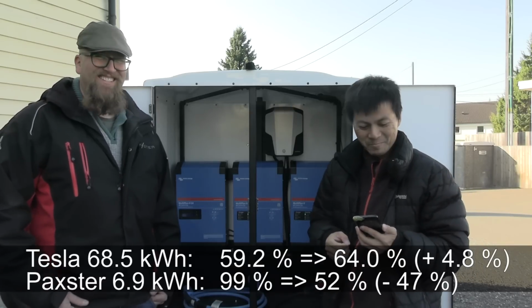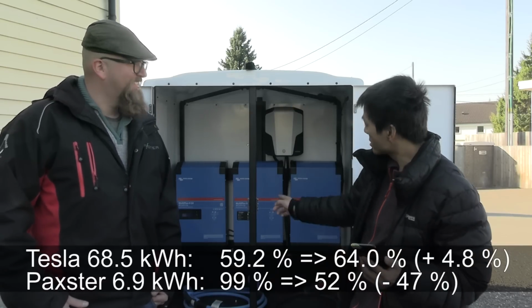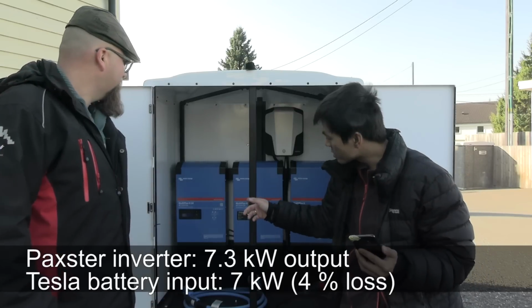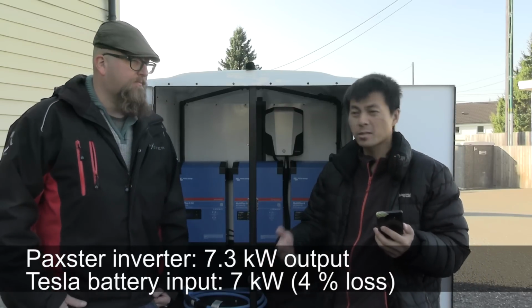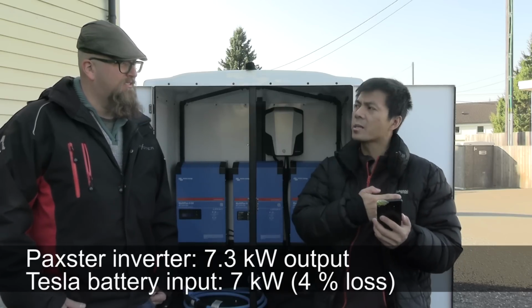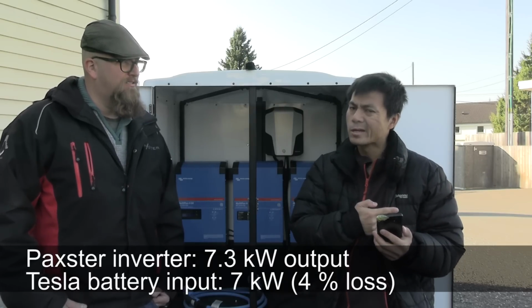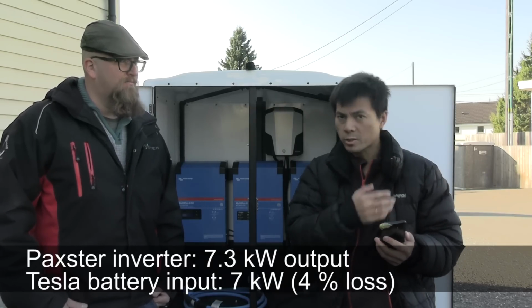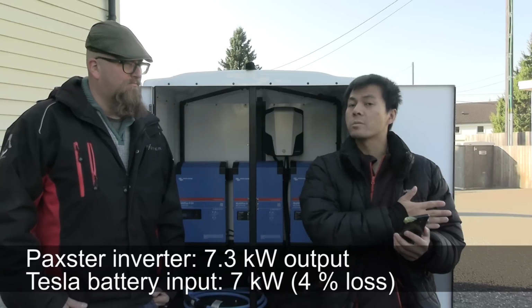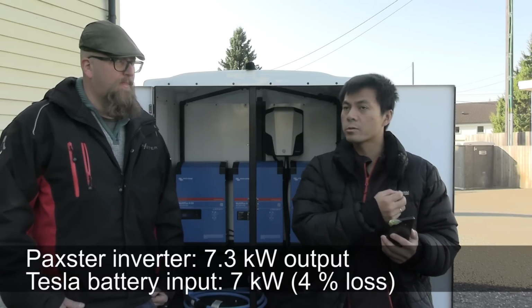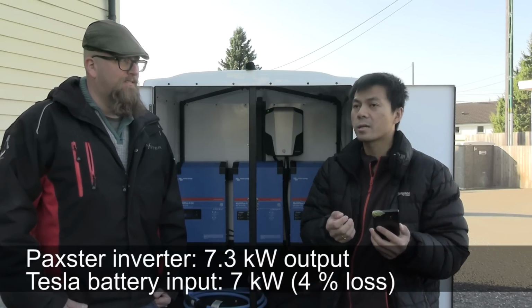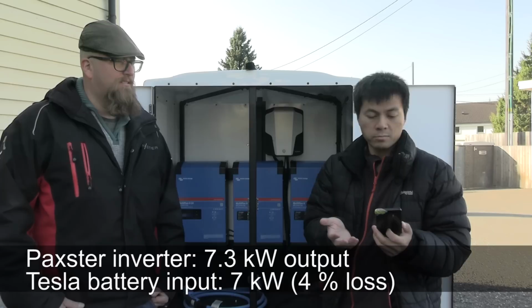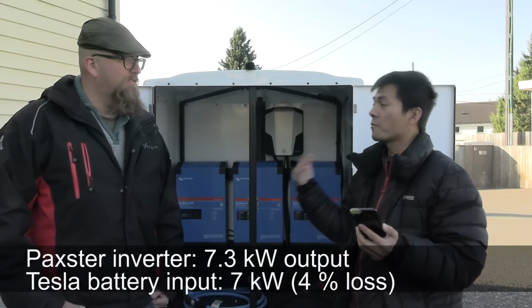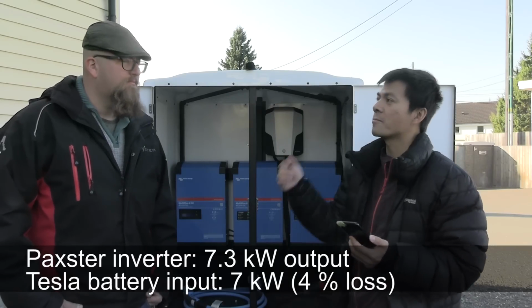We also saw that the inverter outputted 7.3 kilowatts, and that didn't make sense because the Tesla was getting 7 kilowatt into the battery. When the car is just stationary now with the pumps running, it pulls 0.3 kilowatt. So that equals to 4% loss at least, there's a little bit of loss here.